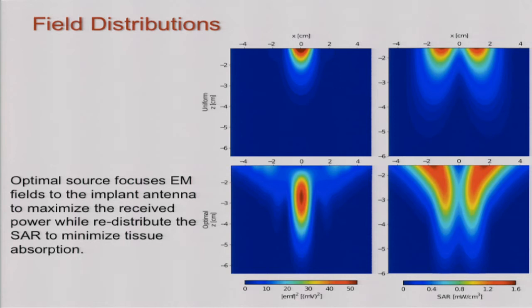So it's 4 centimeters deep inside the tissue. This is the implant location, so the magnetic field kind of focuses to the direction of the implant. This is the tissue absorption—it pushes the hotspot further down inside tissue. Because we can increase the receive power and at the same time make the hotspot deeper, more evenly distributed over the tissue, we're able to get that 10 dB improvement in the transfer efficiency if we can design the transmitter right.